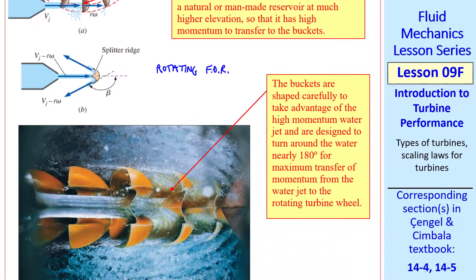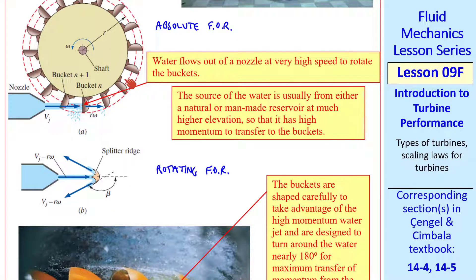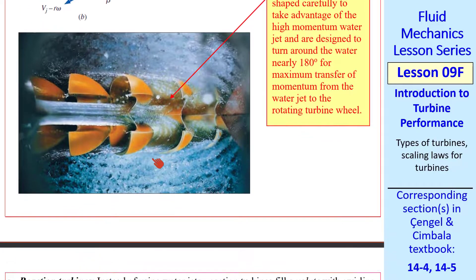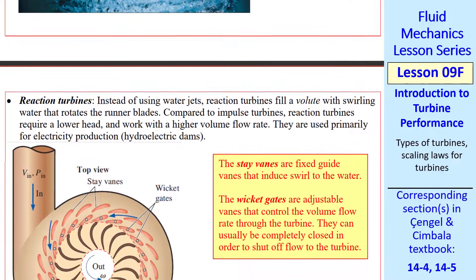The buckets are shaped like cups because you get more force transferred by turning the flow. The jet hits a bucket, generally splits in half, and is turned almost 180 degrees on either half, imparting the most momentum to the bucket as possible. As the Pelton wheel keeps turning, the next bucket is ready to receive the jet. The design of the buckets in Pelton wheel turbines is critical to transfer as much momentum as possible to the rotating wheel.